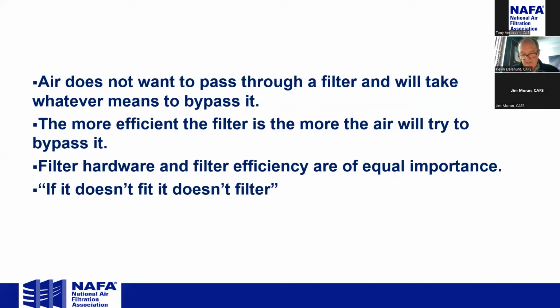And again, going back to COVID, and I'm going to mention it in a little while, but the rallying cry for MERV 13 in systems: if we just think that we can slide out a MERV 6 or MERV 8 filter in a U-channel tracking and put a MERV 13 or MERV 14 in the exact same spot and get the same performance, or the performance you're paying for, we're probably fooling ourselves. Bottom line, if it doesn't fit, it doesn't filter. We have to make sure that all the air goes through the filter.